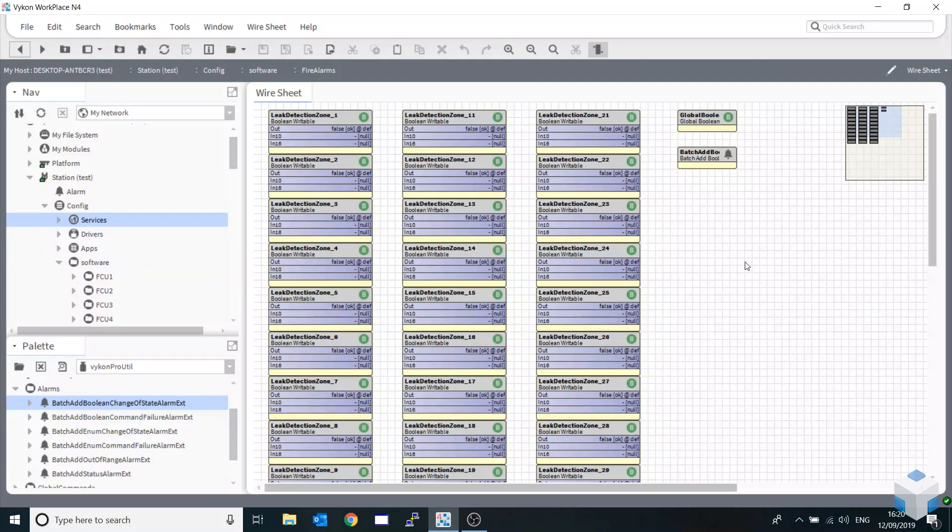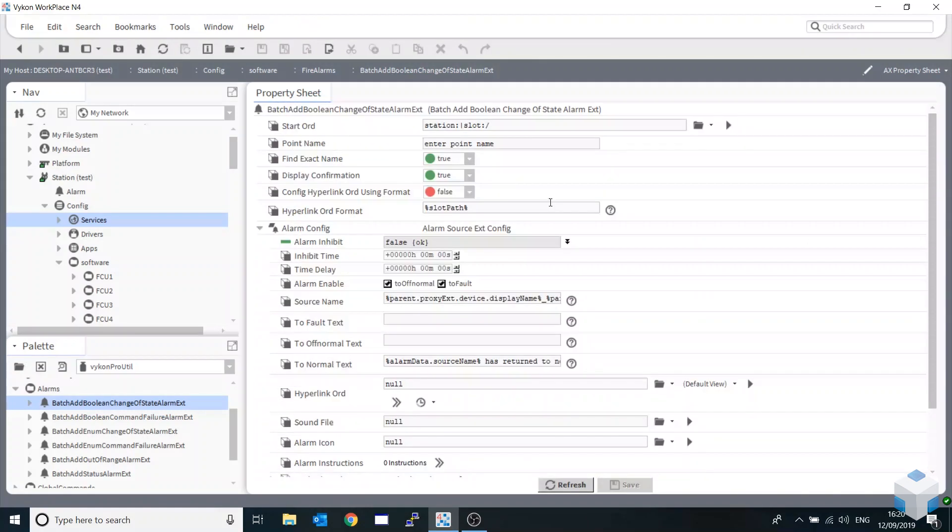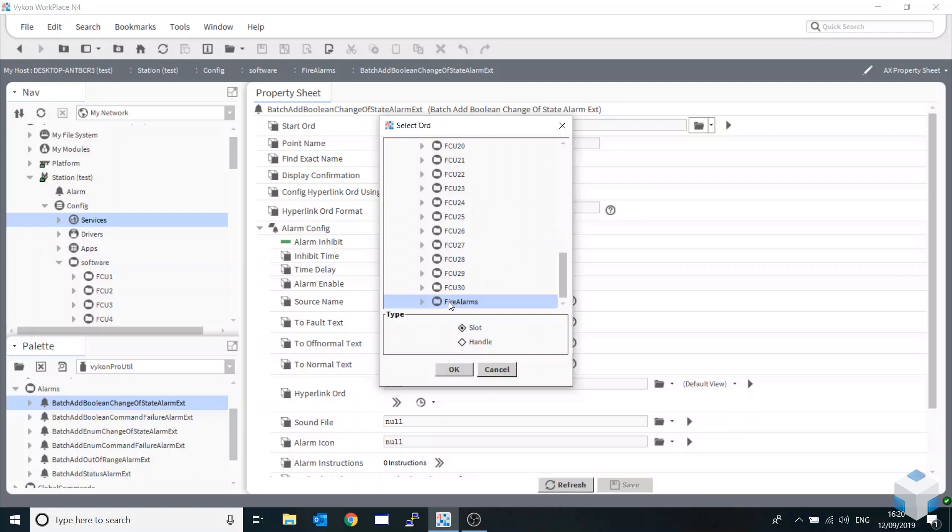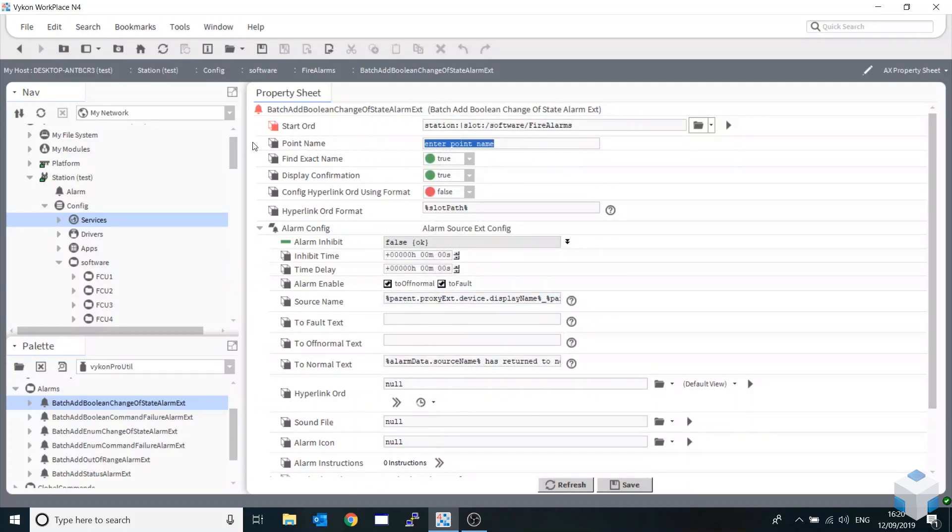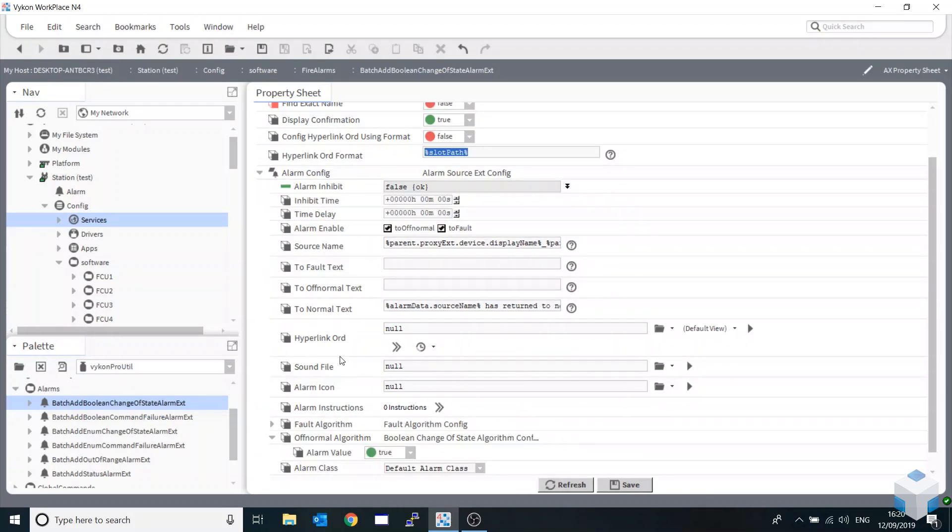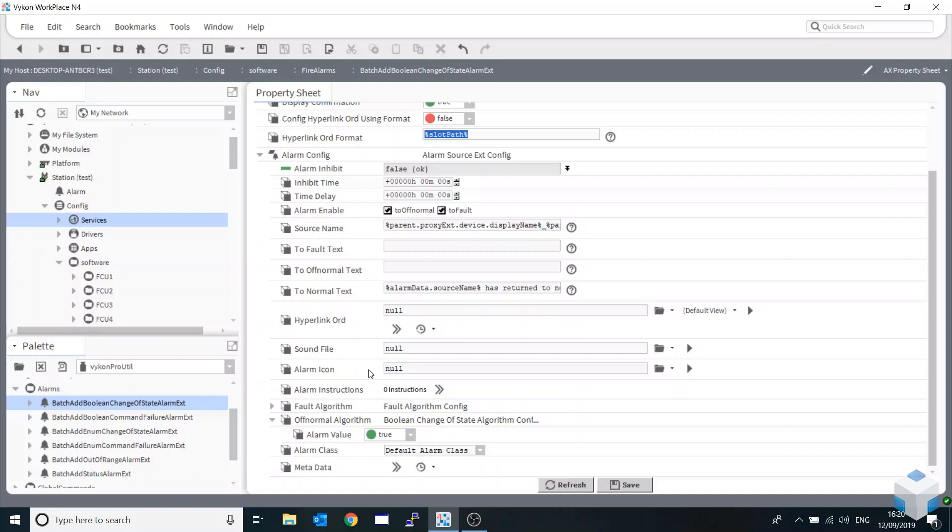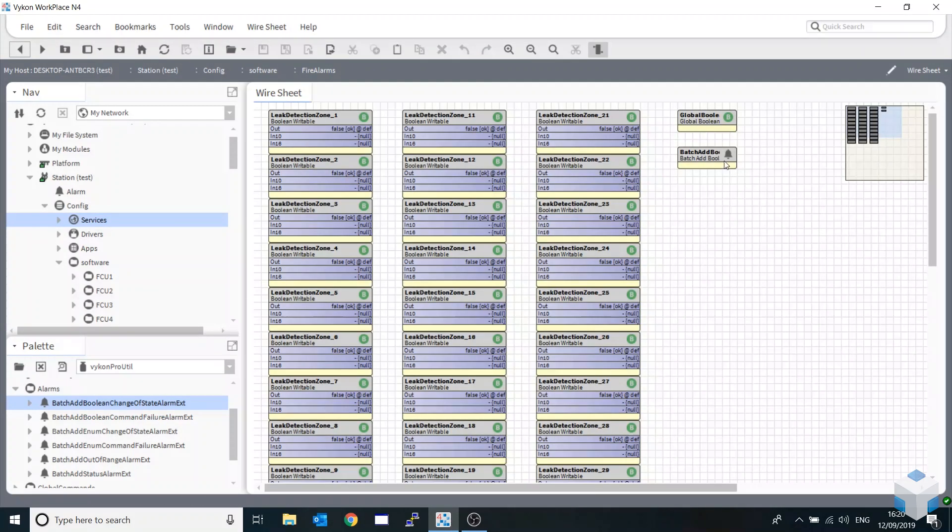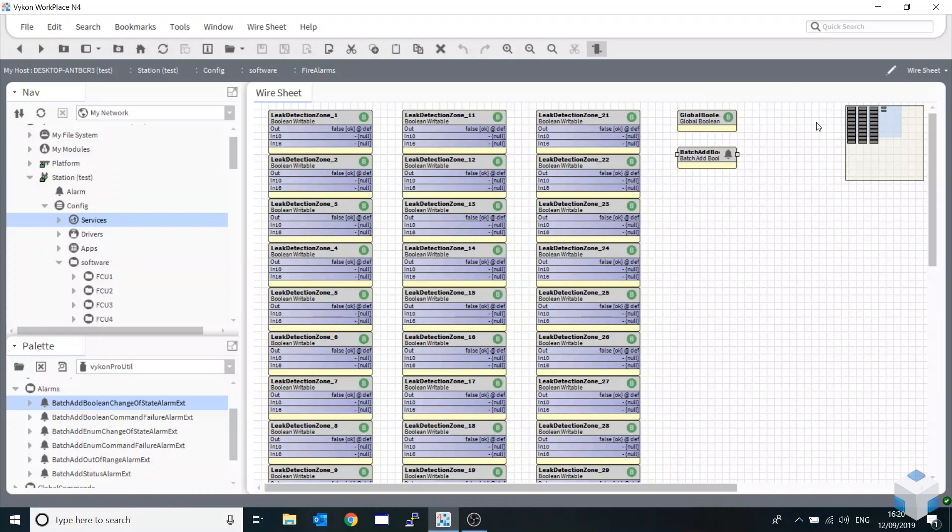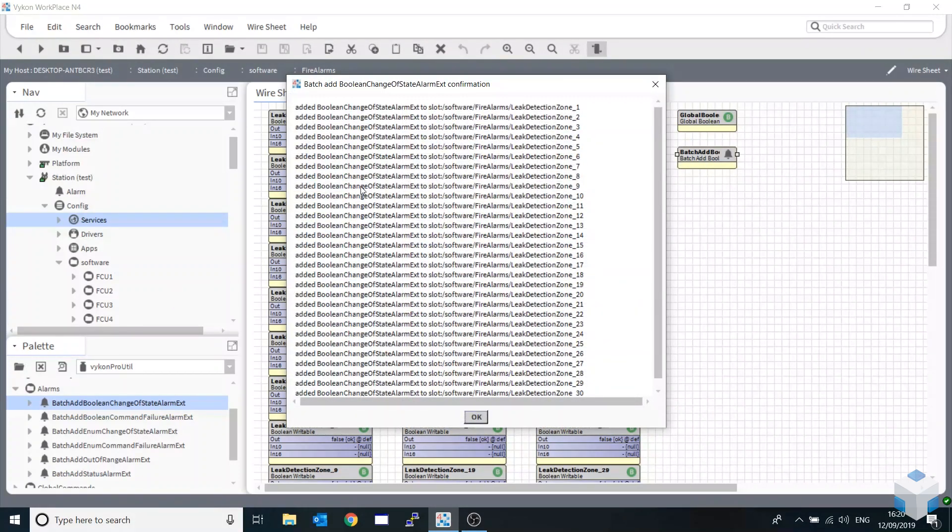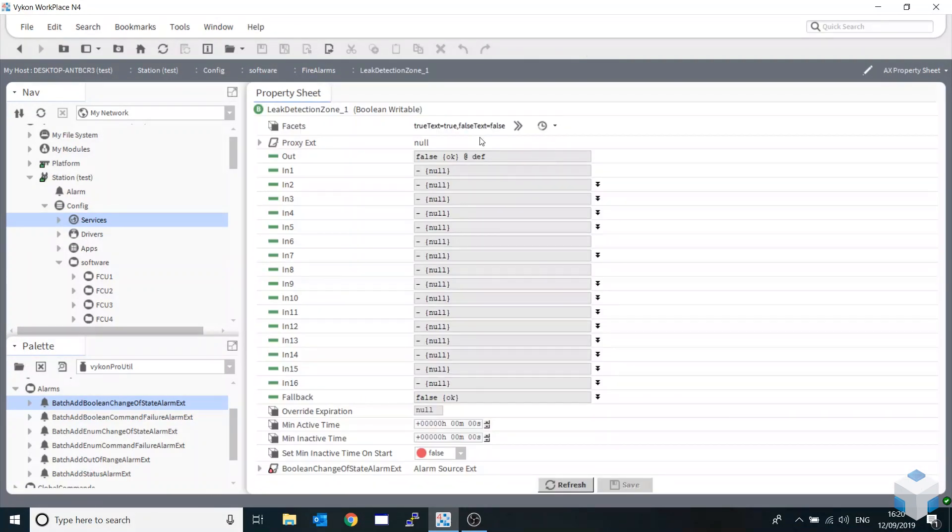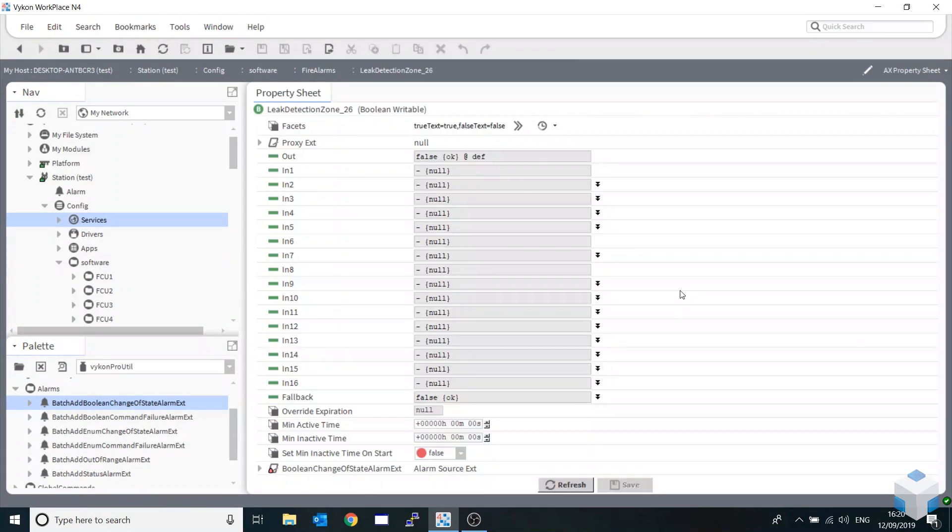Again we'll be using the same format as our previous part of the video - using the naming convention and pointing at a folder to add this alarm block. If I go into our boolean writeables, I've got no alarms in there whatsoever. I'm going to make sure I can add these on mass in retrospect of what I need to do. Go into our batch module, find the folder I want to point it at, enter our point name using an asterisk as a wildcard. Remove find exact name, display confirmation. Now we can do the whole configuration - I could put a hyperlink in there, put text for on and off normal text. I'm just going to save that, come back out, right click actions and simply add alarm extension.